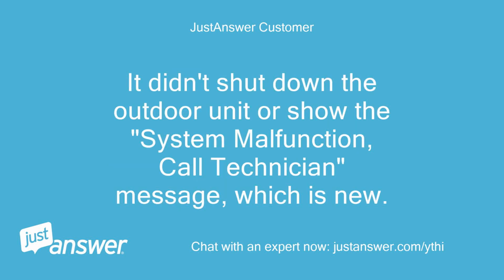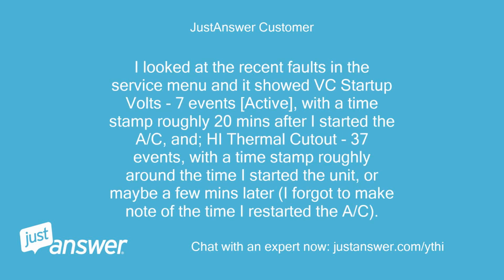It didn't shut down the outdoor unit or show the system malfunction, call technician message, which is new. I looked at the recent faults in the service menu and it showed VC Startup Volts, 7 events, active, with a timestamp roughly 20 minutes after I started the AC, and high thermal cutout, 37 events, with a timestamp roughly around the time I started the unit, or maybe a few minutes later. I forgot to make note of the time I restarted the AC.